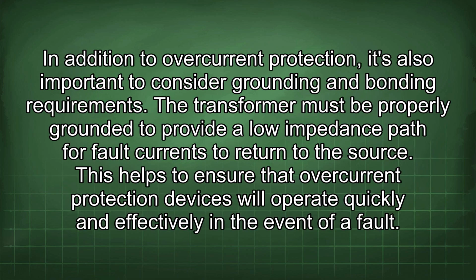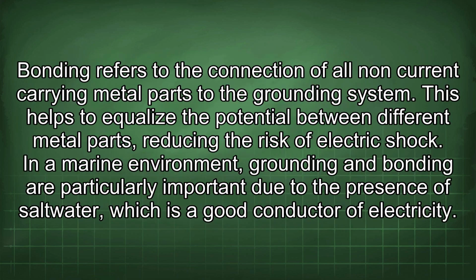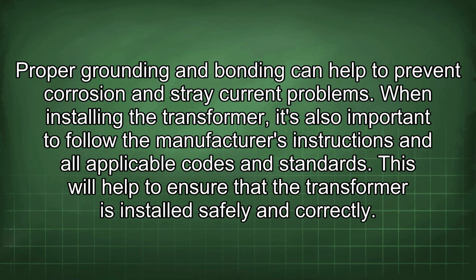In addition to overcurrent protection, it's also important to consider grounding and bonding requirements. The transformer must be properly grounded to provide a low impedance path for fault currents to return to the source. This helps to ensure that overcurrent protection devices will operate quickly and effectively in the event of a fault. Bonding refers to the connection of all non-current carrying metal parts to the grounding system. This helps to equalize the potential between different metal parts, reducing the risk of electric shock. In a marine environment, grounding and bonding are particularly important due to the presence of salt water, which is a good conductor of electricity. Proper grounding and bonding can help to prevent corrosion and stray current problems.